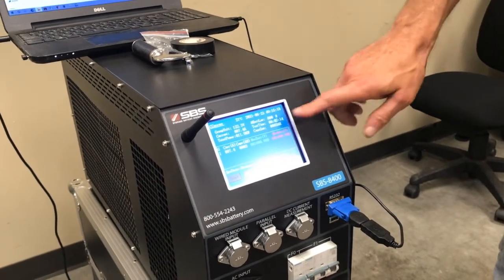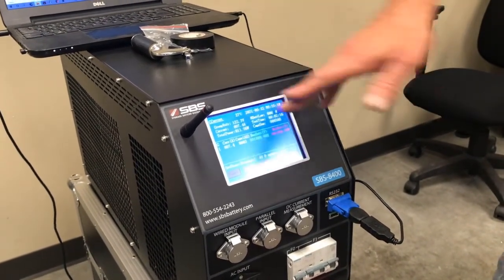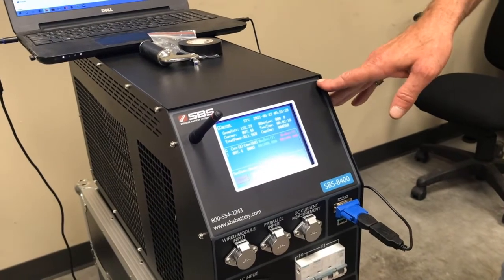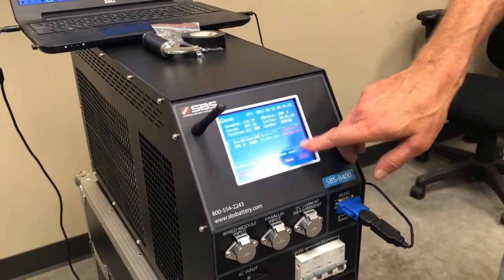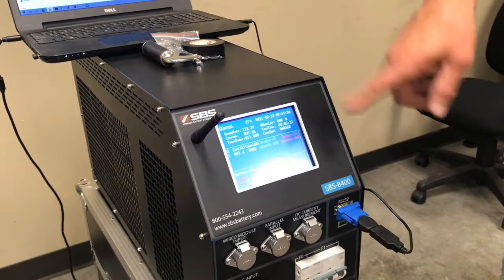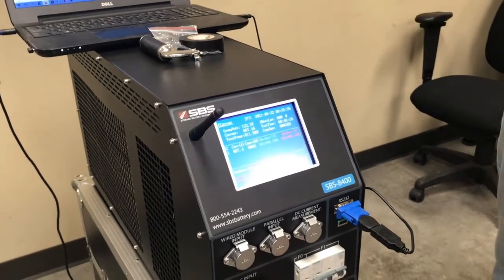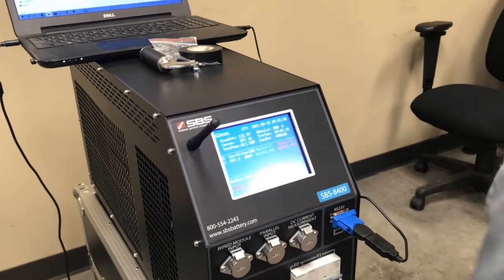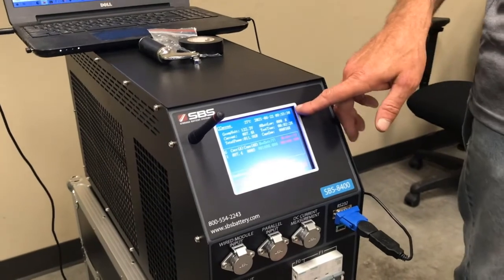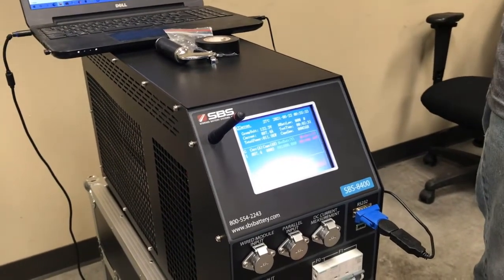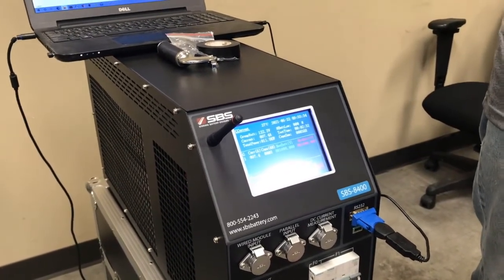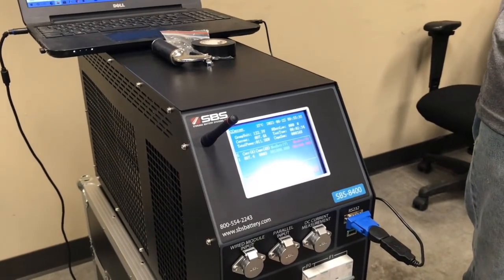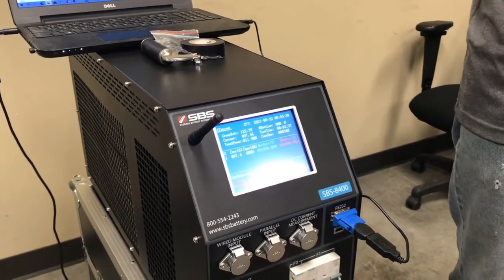Now the test is going to run for 1 hour and 30 minutes that we programmed. It's going to run to 105.0 volts for the entire battery system. And we'll be able to measure the amount of time that the battery lasts until it hits that 105. And we want that group low voltage to be the shutdown parameter that terminates the test.